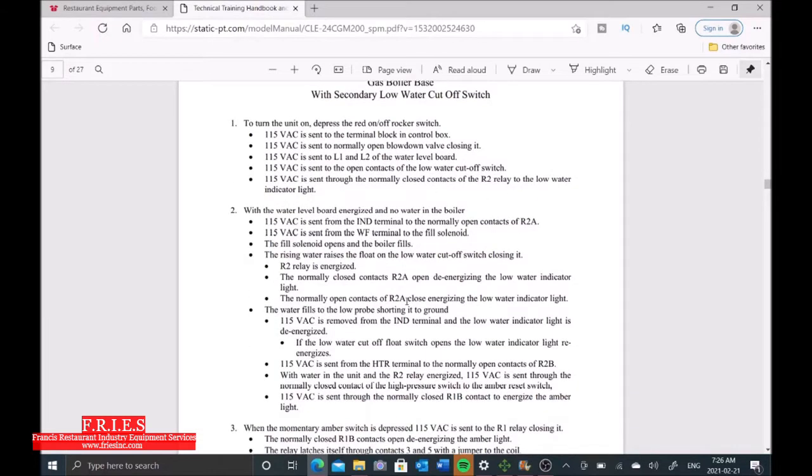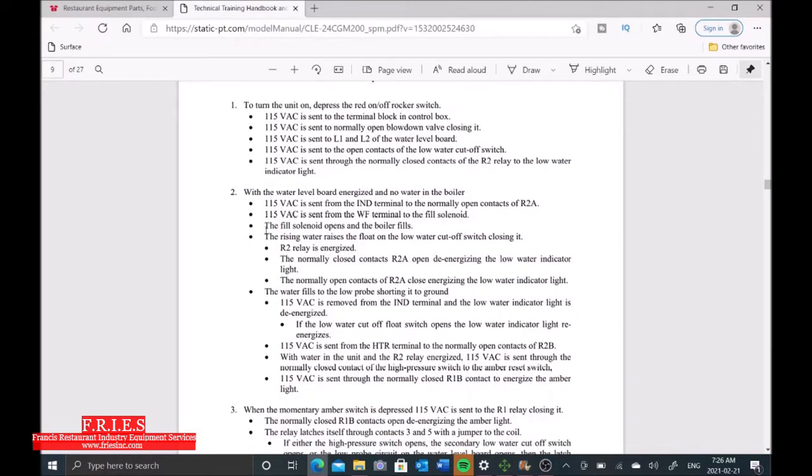Let's go to our sequence for filling. The fill solenoid opens and fills the boiler. The rising water on the float raises the float on the low water cutoff switch, closing it. Once that happens, this low water indicator light should turn off. Then the water fills to the low probe, shorting it to ground, and that should also remove the low water light.